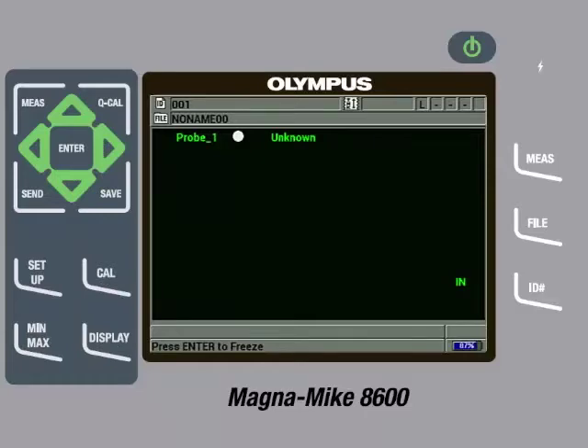The Magna-Mike 8600 can auto-detect the different sized target balls, but it cannot auto-detect the disc or wire targets. Therefore, we will need to tell the instrument what target we are going to use. To do this, press the Setup key.